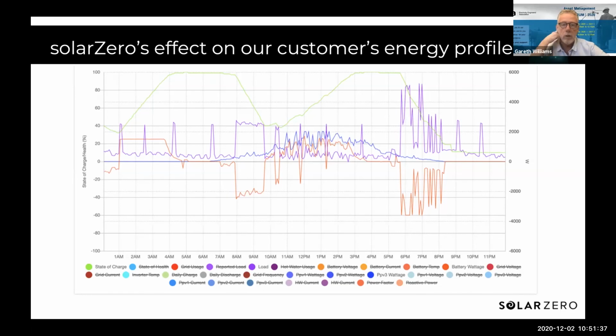The green line on the top is showing the battery state of charge. The battery has reached about a 30% state of charge in the early morning. We charge it up from the grid to 100%. It discharges back down to about 40% after the morning peak, then charges up during the day, reaches fully charged in this case by right on 3 p.m, which is useful. Then it discharges all the way down to about 10% through the evening and into the night.